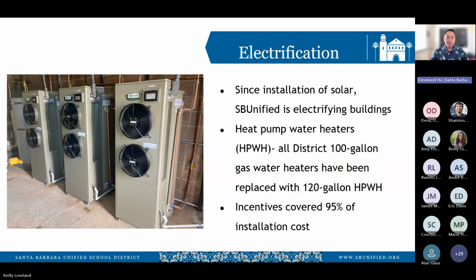One benefit and also potential problem: most water heaters at school facilities are typically in really small rooms with little to no ventilation. Since these heat pump water heaters discharge cold air, a lot of these rooms got too cold, and the heaters have to defrost and not work efficiently.